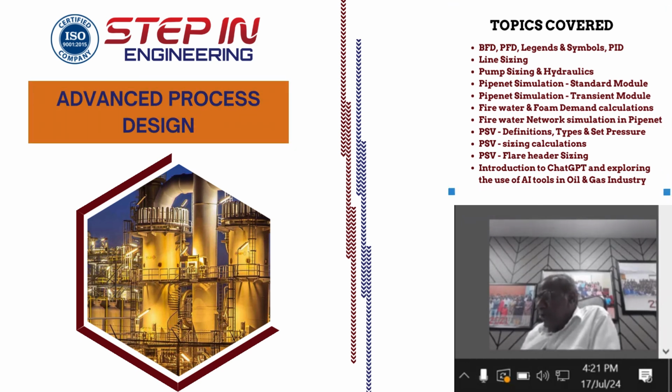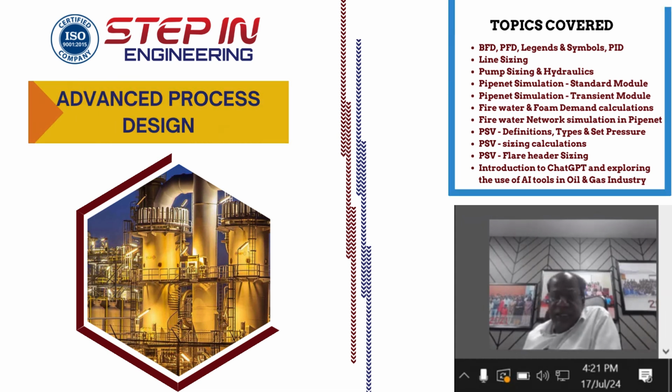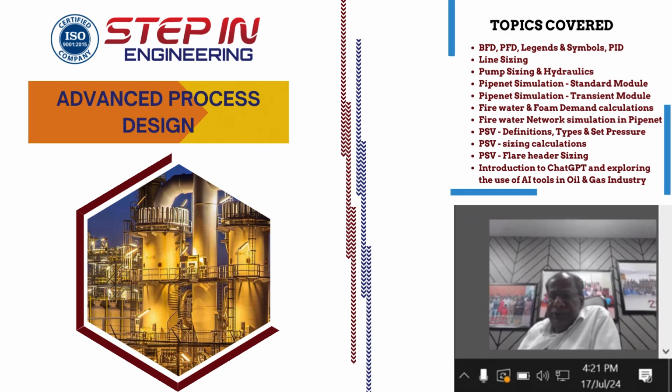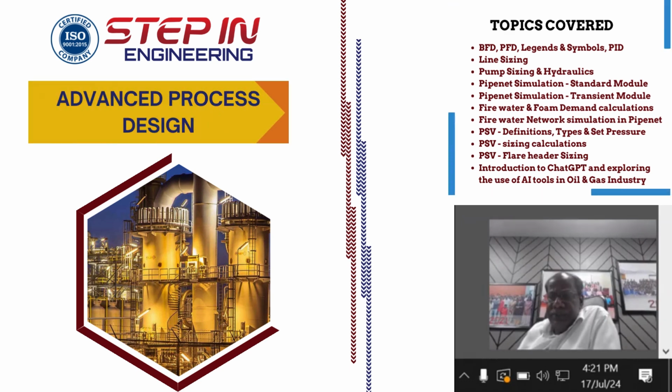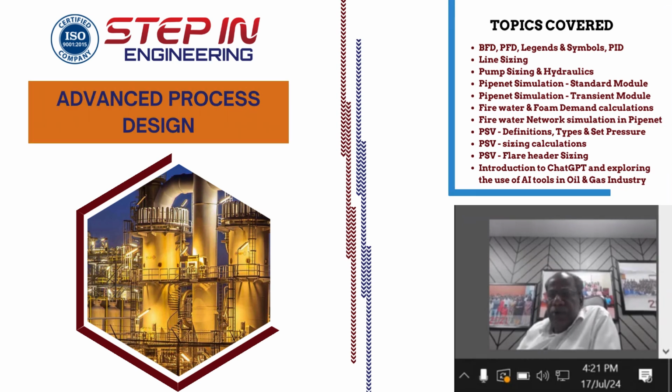Then comes the third day, which is pumps and hydraulics. Pump sizing and hydraulics is a very important subject. The most important concept is NPSH, net positive suction head available. If you don't know how to do the NPSH calculation, the pump will not work. You will make the data sheet and buy the pump, finally you put it in service, and it will not work. Then you go back and do the postmortem, and you find that the NPSH is not correct, the vapor pressure was not taken.